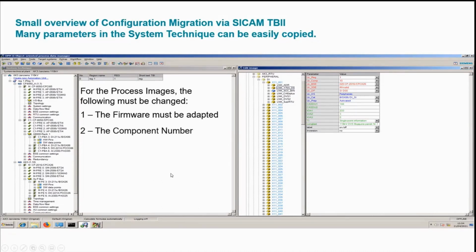So the next step is to point it now to the CP8050. So to change, in this case, the component number, it will no longer be 10, but 1. And in this case, remember the binary inputs are not coming from the master module, which has address 20 also. It will be coming from the extended processing, from the C1. So I need to change it here as well. So when I do it, then there are no more errors here.